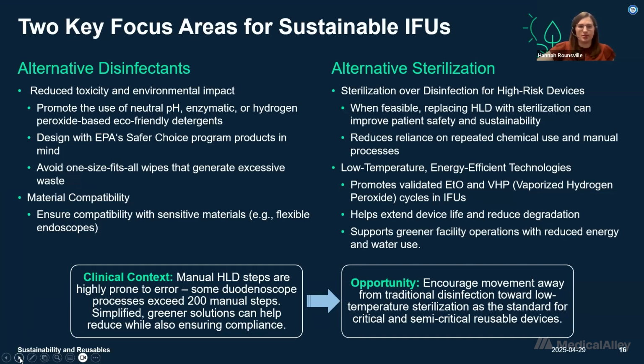Lower temperature sterilization is also more compatible with more materials now than ever, allowing sensitive devices to be sterilized without compromising their durability, and then reduce chemical exposure for healthcare workers and lowering environmental toxicity. For an example of this type of approach, let's consider devices like flexible endoscopes, which often require over 200 steps during manual reprocessing. This complexity increases the risk of human error and resource waste. So by simplifying reprocessing steps and incorporating safer automated sterilization options into these IFUs, we can improve compliance and consistency, lessen our environmental footprint, and maintain the highest infection control standards possible.